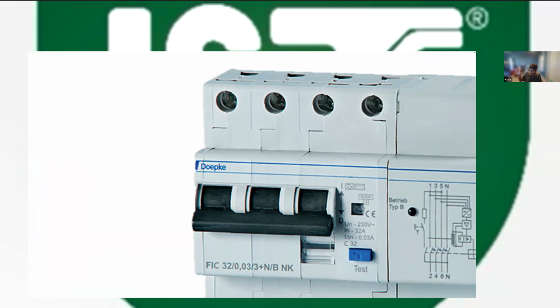So you need to verify that the RCD's characteristic itself is type B. So tell your guys on site, don't get confused between the RCD's characteristic and the overcurrent characteristic. They are two very, very different things.